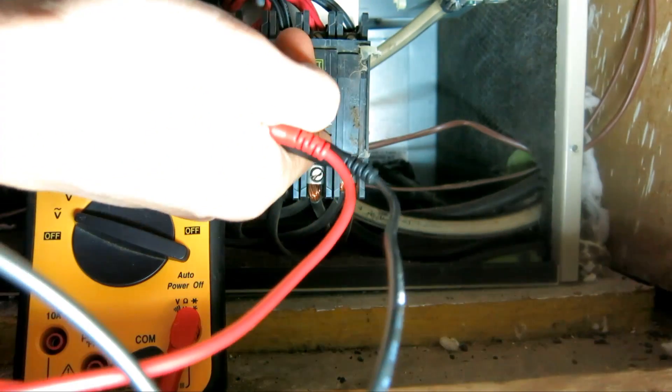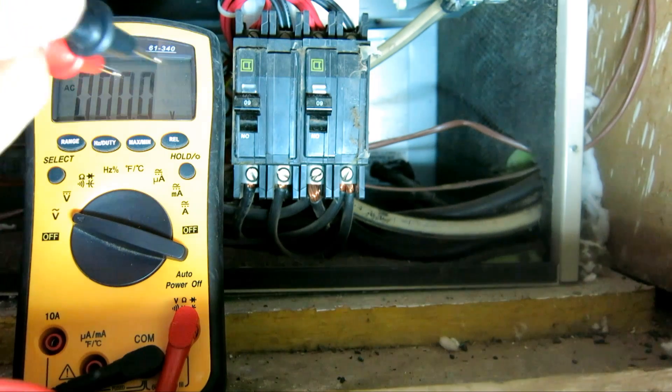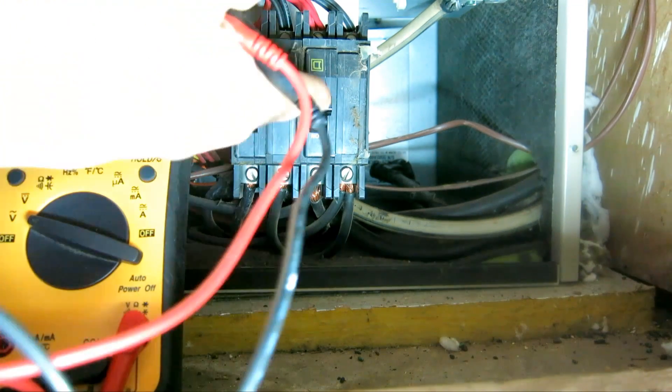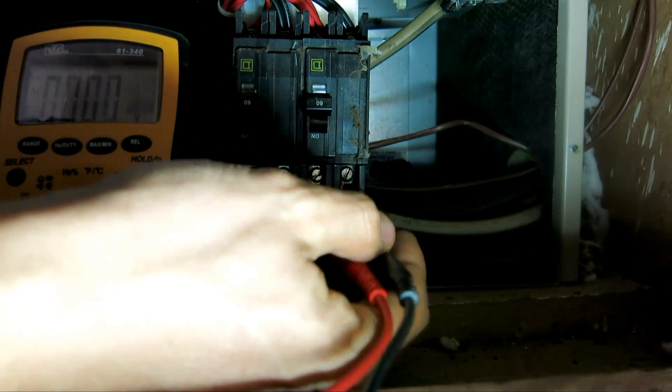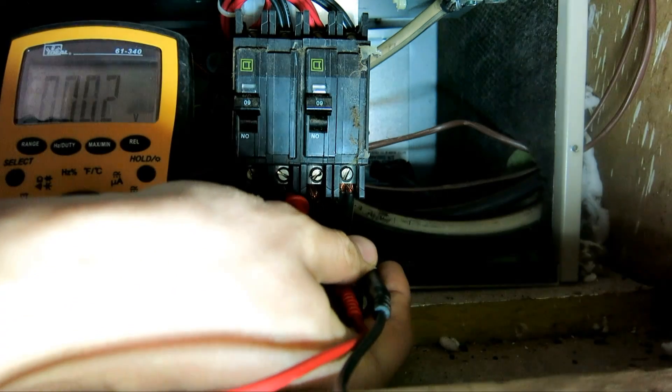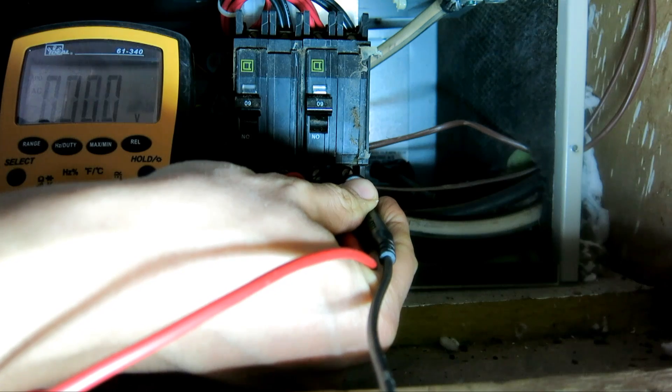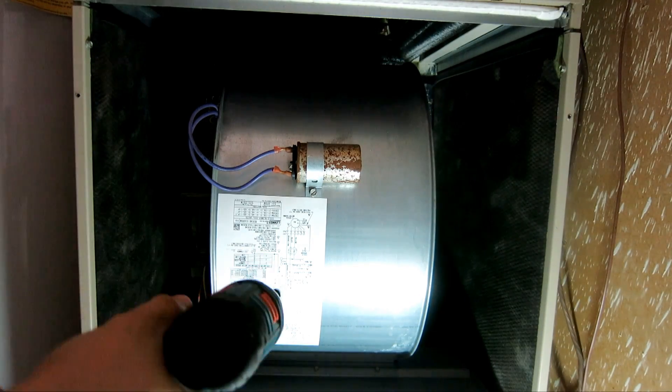First, let's check to make sure there's no more power going to this unit, even though I already switched off the breaker. I'll switch these two off and measure the leads on the bottom where the power comes in. As you can see, it's zero volts.